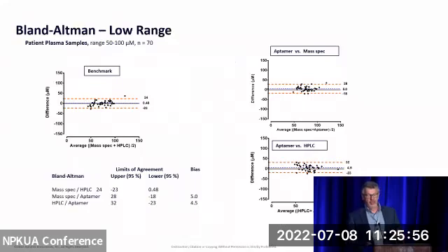So that's shown here, which is really comparing to, again, HPLC or mass spec at the low concentrations in the 50 micromolar range, to make sure that we can use this for patients who are being treated with therapies like Kuvan.